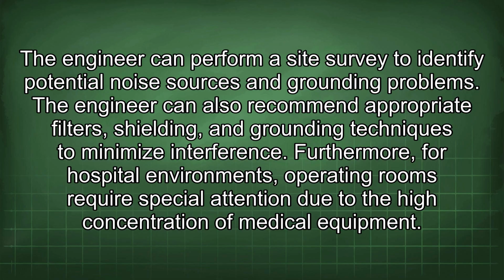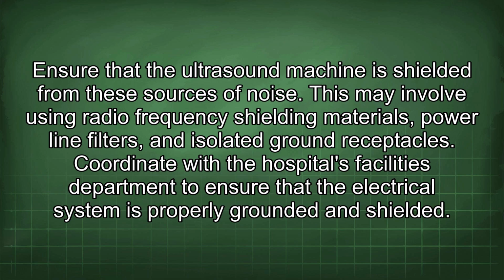Furthermore, for hospital environments, operating rooms require special attention due to the high concentration of medical equipment. Ensure that the ultrasound machine is shielded from these sources of noise. This may involve using radio frequency shielding materials, power line filters, and isolated ground receptacles. Coordinate with the hospital's facilities department to ensure that the electrical system is properly grounded and shielded.